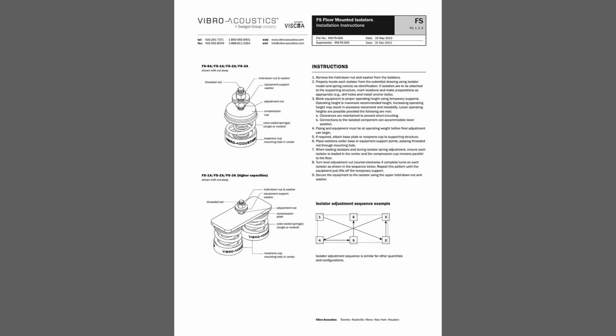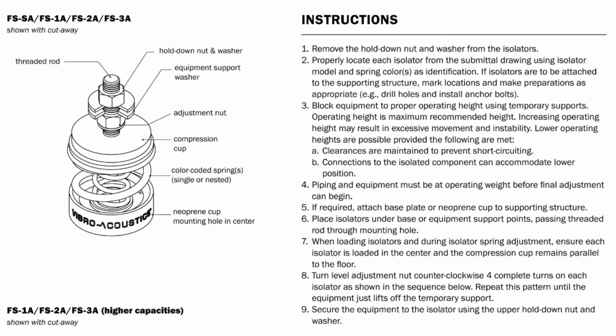Now taking a look at the installation instructions for the floor springs, we'll zoom in so we can see them better. Some of these instructions were repeated on the inertia-based installation instructions. We'll want to check to make sure the right isolators are in the right locations based on the selections shown in the submittal. For the heating water pumps, they're all the same, so that'll be easy.